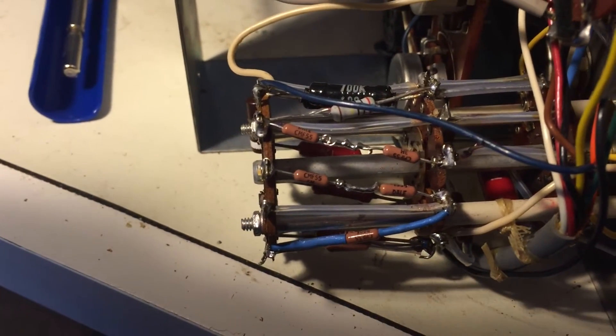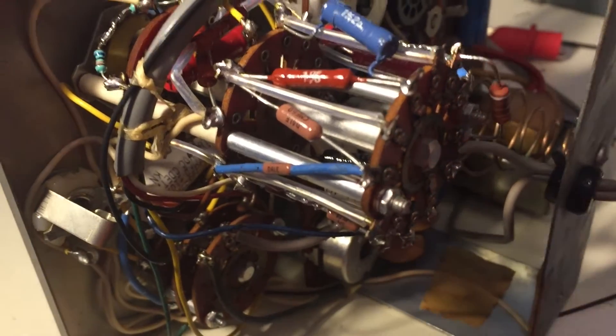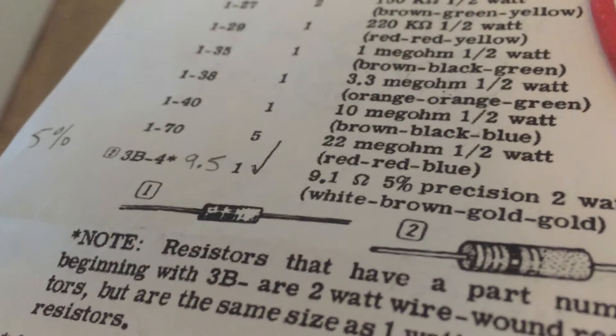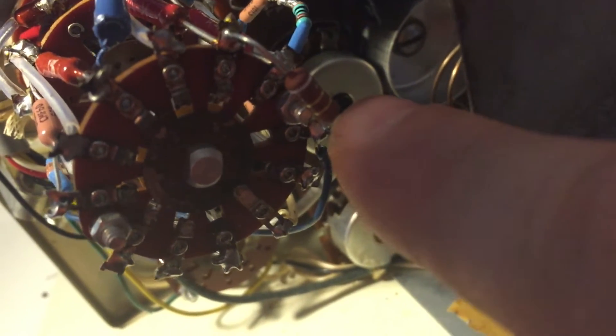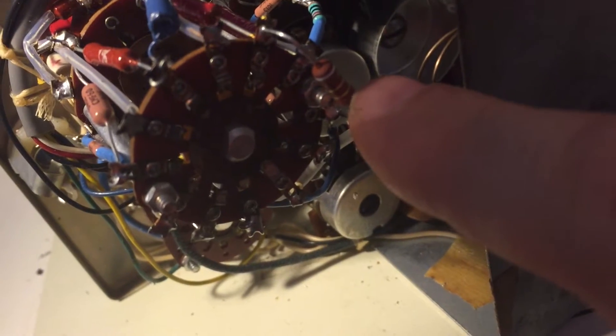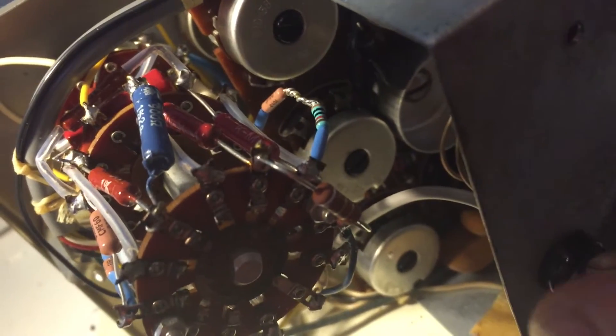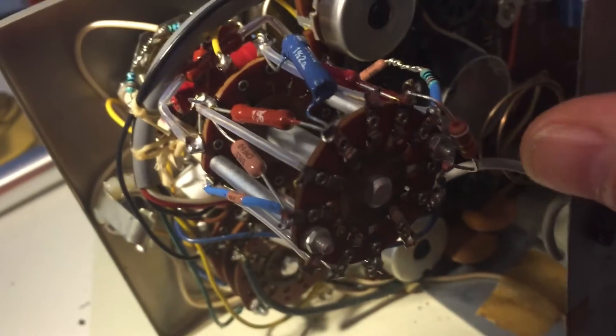Now we have the 7 meg and the 2 meg completed and tested. Now we'll proceed to the final resistors. Not only do I have every resistor replaced perfectly within 1% specification, but I've also got a perfect 9.1 ohm resistor right here. And that was the one up here and it was reading 9.5. And while it was within 5% tolerance, I was able to get my hands on a 2 watt 9.1 that read exactly 9.1 on a very highly calibrated measurement. And I put that in there. So that helps for the measuring resistance. Now I've got that down pack. But all these measure absolutely perfectly on the multimeter. So we're ready to do calibration.